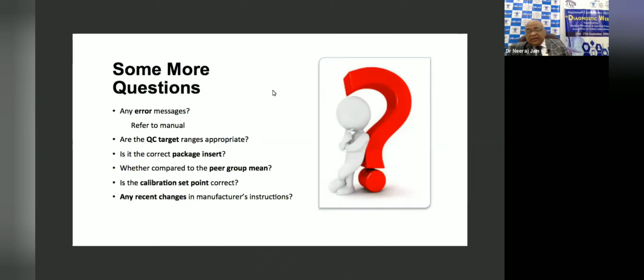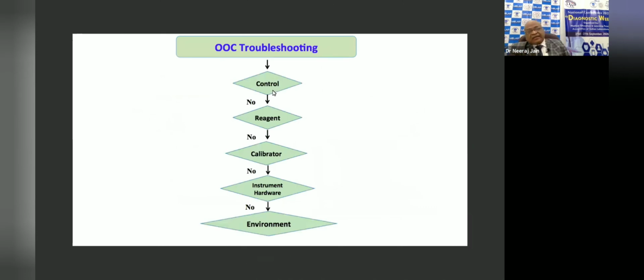And sometimes, a very common situation, we have changed the lot of control, but people are using the old insert. They are thinking this comparison chart is the same. We have to see that we are using the package insert of the new lot only. Whether the calibration set point is correct or not, any error message on the machine, all these things we check, and then we take appropriate action. When we troubleshoot, we have to see if something has happened with the control, or with the reagent, or with the calibrator, or with the instrument hardware, or in the environmental conditions, or something related to the operator.